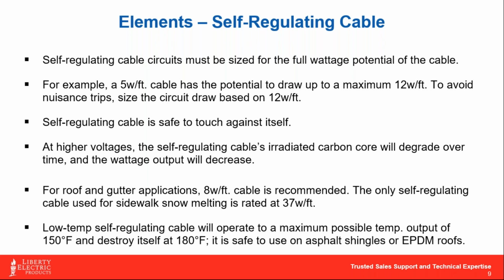And speaking about the commercial application, typically we want to be around 8 watts a foot is where we standard design for commercial application. And another reason for that is that you can also suffer voltage deration. Most heat cable manufacturers are going to design their product based around 240 volt. So when we feed it 277, let's say on the high side, instead of that 8 watt a foot cable putting out 8 watts a foot at 50 F, it may actually be putting out 9 to 9.3 watts a foot, maybe even up to 9.5 at like 277 volts. So it's going to run hotter, which is a great thing when you're trying to melt snow.